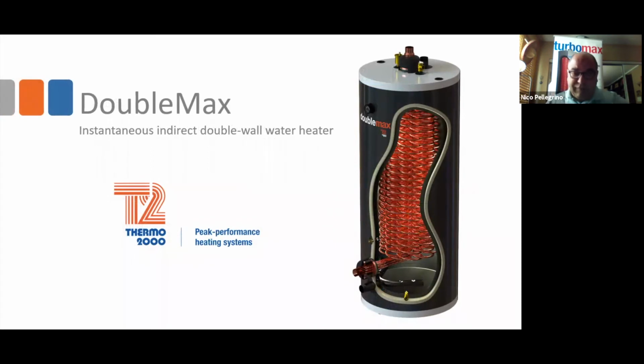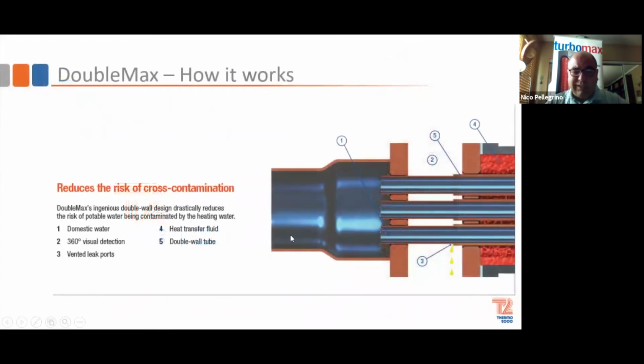Now, in Vancouver, the Turbomax cannot be installed in commercial buildings, and that's a written rule. And this is why we have the Double Max. It's exactly like the Turbomax, only now it's a double wall coil. The rule for double wall is it has to have 360-degree visual detection on the outside of the tank so that if there is a breach, it's visible. So this is how we accommodate it. We do a double flange and a double tube.